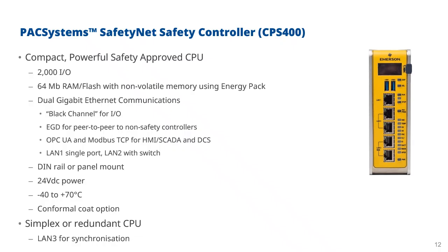Now we also support standard EGD, which gives us the capability for peer-to-peer communications to non-safety controllers. We support OPC-UA, which would be our preferred communications protocol, because that can be secured and encrypted, but we do also support Modbus TCP as well. Again, typically with a system, there wouldn't be any writes to the system, so normally this data would be one way from the safety system to an external control system or DCS or whatever.